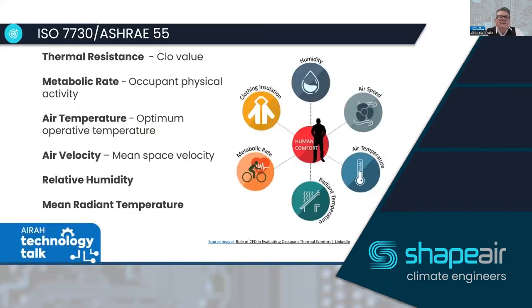ISO 7730 and ASHRAE 55 are very similar or essentially the same. They are an amalgam of six elements: the thermal resistance (CLO value), the metabolic rate, the physical activity, the air temperature or operative temperature, the air velocity and mean space velocity, and the relative humidity and mean radiant temperature.